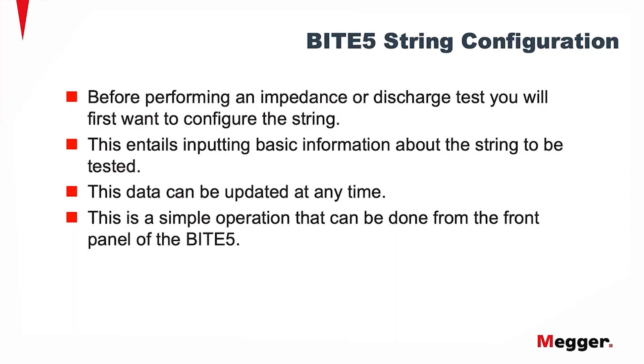Before performing an impedance or a discharge test, you'll first want to configure the string. This entails inputting basic information about the string to be tested. This data can be updated at any time and is a simple operation that can be done from the front panel of the BITE5.